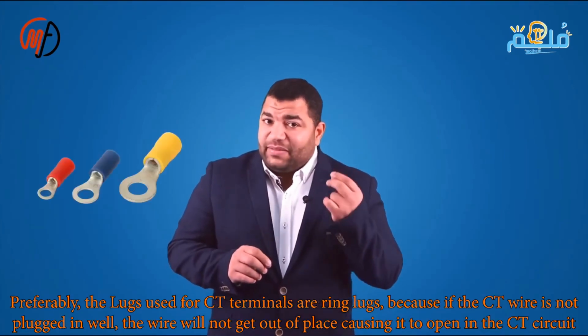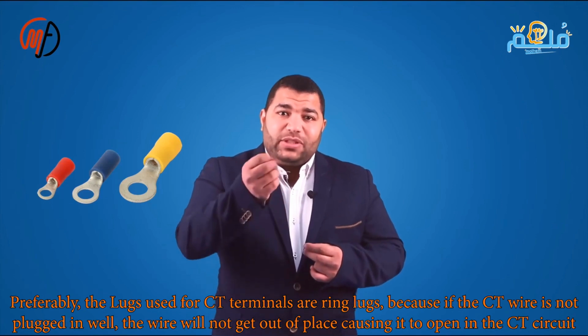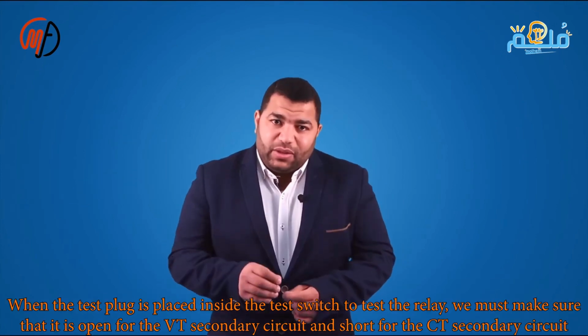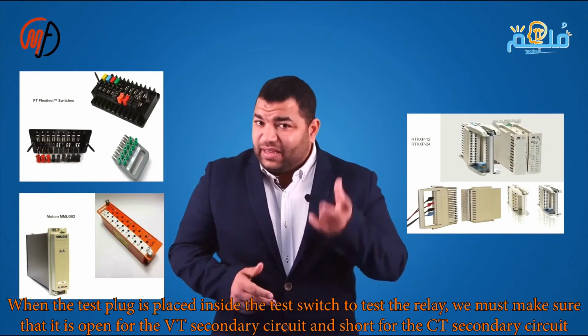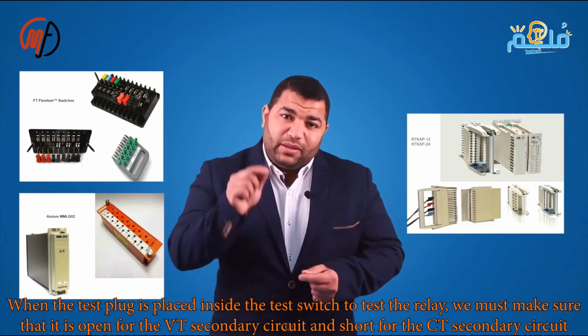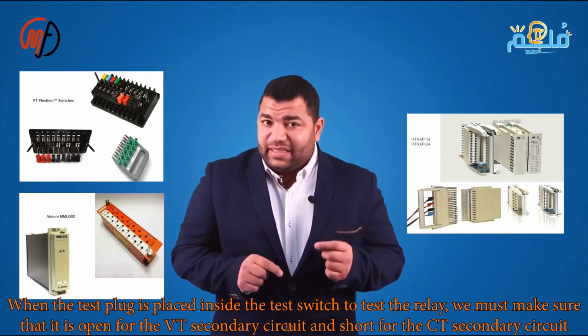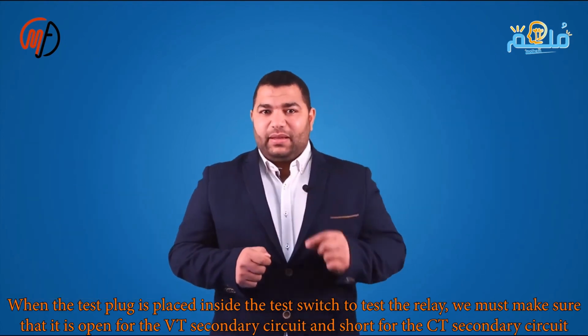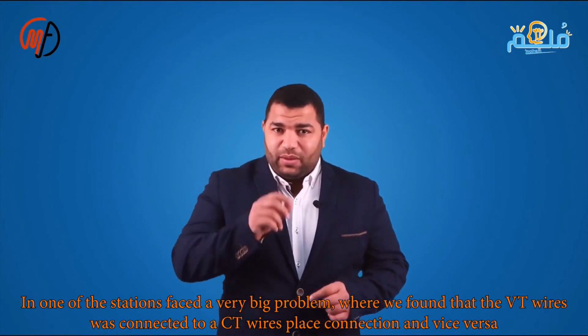Place the test plug in the test switch to open the VT secondary and short the CT secondary. We found VT wires connected to the CT location in the test switch and CT wires to the VT location. This causes an open circuit for CT and a short for VT, which is very dangerous. It highlights the importance of testing before operation.